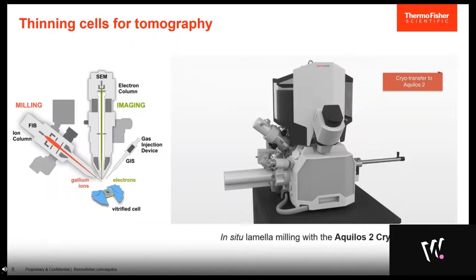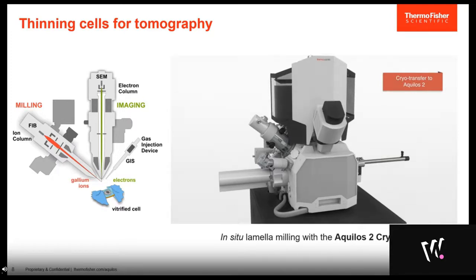This slide shows our Aquilos II CryoFIB system — a dedicated device for preparing samples for electron tomography. It is a dual-beam instrument, meaning there are two columns on this system: one electron column for scanning electron microscopy, and one focused ion beam column. The FIB column produces a very fine, focused beam of gallium ions that can be used to ablate material from a cellular sample. The next animation will show how this works.